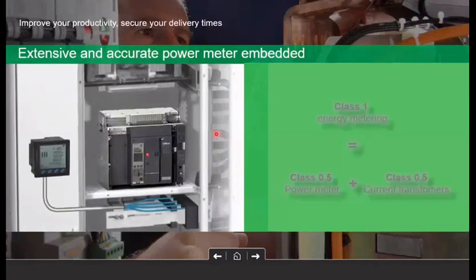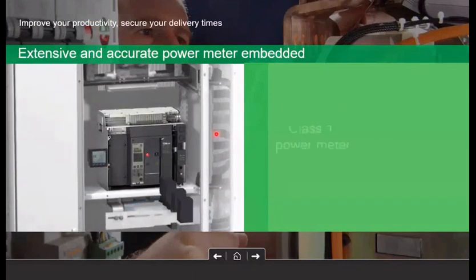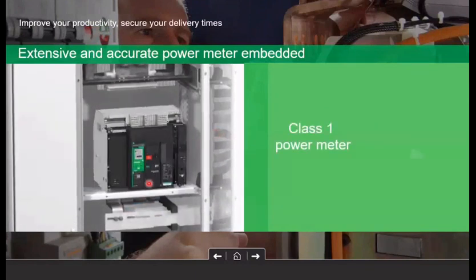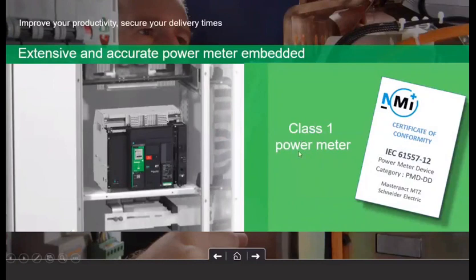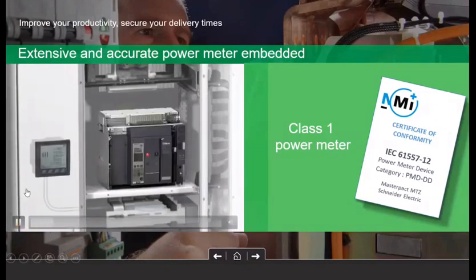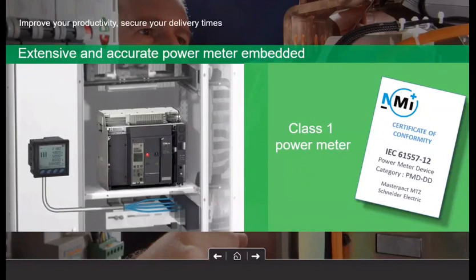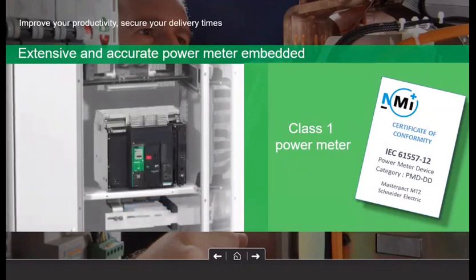So in addition to these digital modules, what is there in MTZ? You can see in the video, we have class 1 energy accuracy. The class 1 accuracy for the energy and power metering parameters in the MTZ, you will get by default, and the accuracy for voltage and current is class 0.5. So you don't need to go for external CTs, you don't need external meters, all the wiring accessories, even the MCB required for the external CTs and meter, that is not required at all in MTZ. MTZ comes with class 0.5 accuracy for voltage and current and class 1 accuracy for the energy parameters.